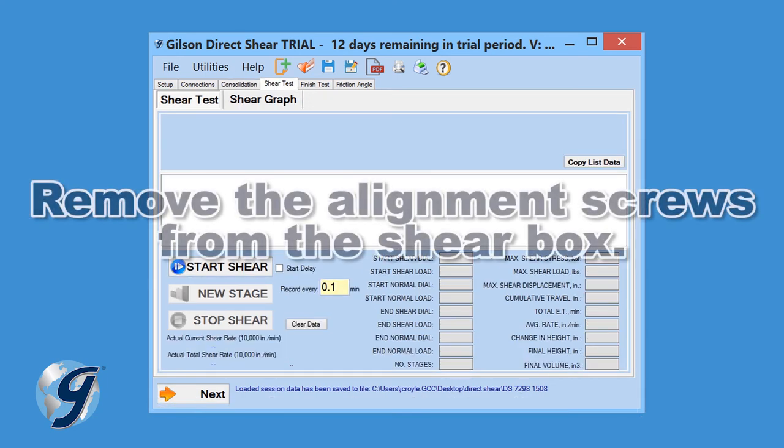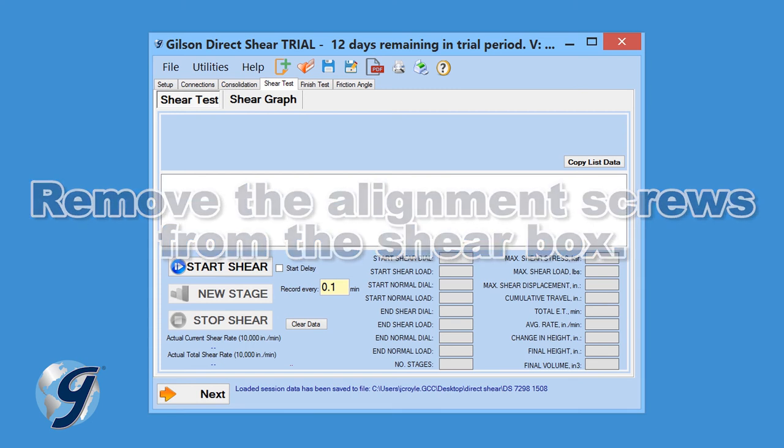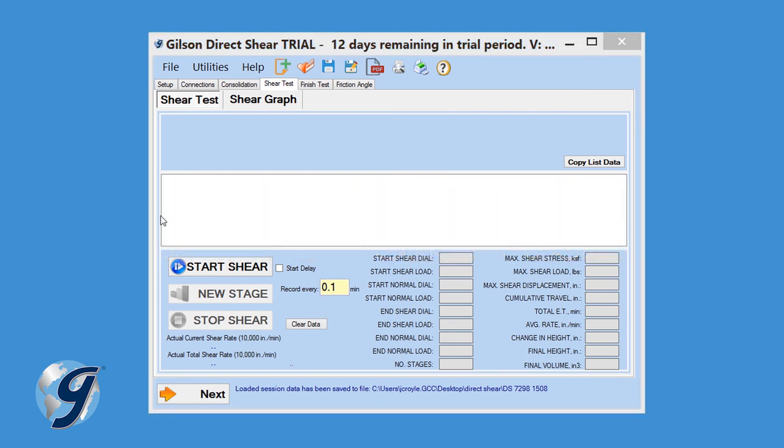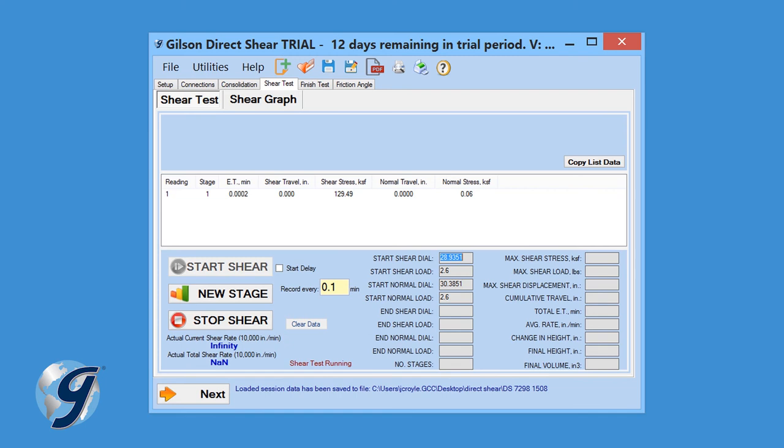Remove the alignment screws from the shear box and click Start Shear in the Shear Test tab. A dialog box will appear with the pre-shear checklist. Ensure that all items on the checklist have been completed. Select OK and begin the shear phase.